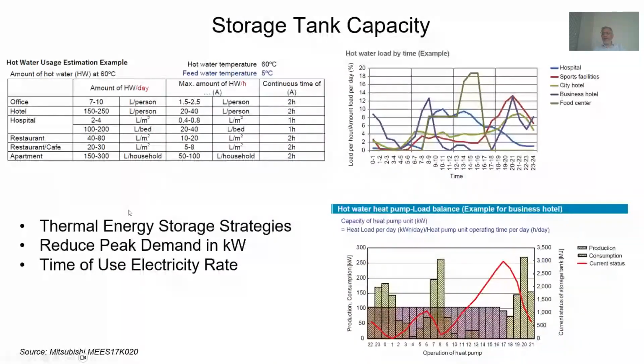Typical again. So when we are designing our system, or we are considering using a domestic hot water tank that can provide hot water for a building, we need to see what's best for us. We want to go for thermal storage strategies, the best thermal storage option available. It will help us reduce the size of the machine, and we have to make sure that we are able to provide the required hot water for those peak demands. So our storage capacity should be good enough to help it out on those things.